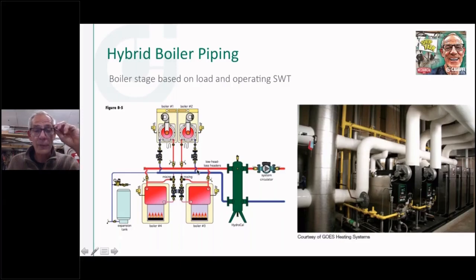And this is a clever one. This is actually a job that we did down in Texas, I believe it was. Kevin might remember this, one of our reps down there. And this is what's called hybrid boiler piping. There are 5 boilers in this picture. This drawing shows 4, but we had the drawing before the picture was mailed to us. What they did here is they mixed 2 different types of boilers. They've got condensing boilers, the first 2 stages here, and the rest are just conventional boilers.